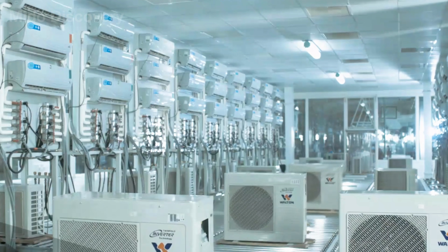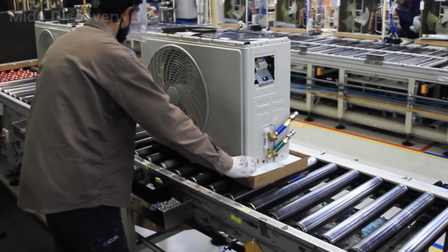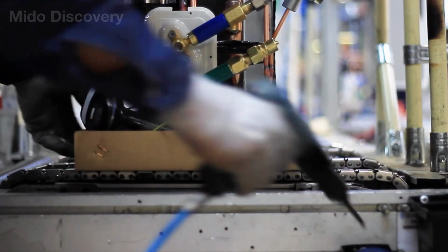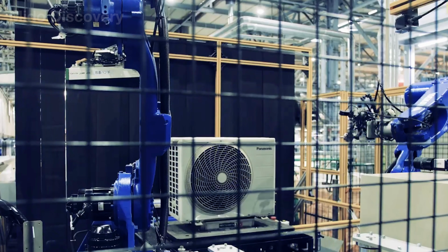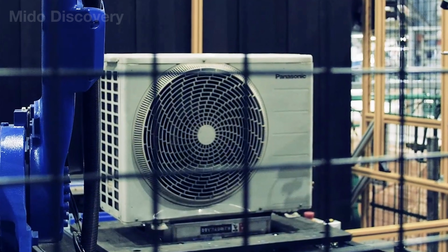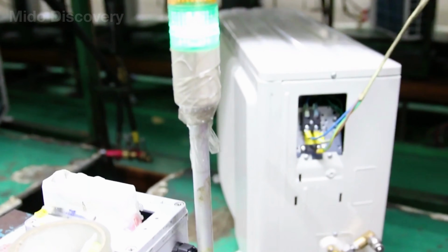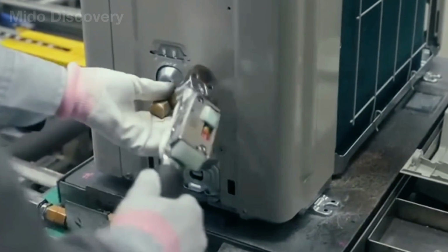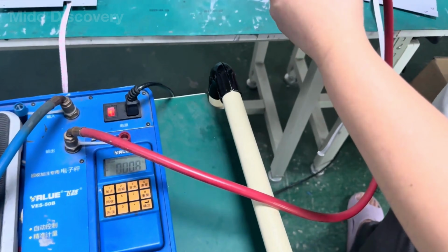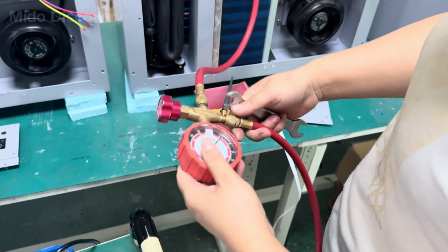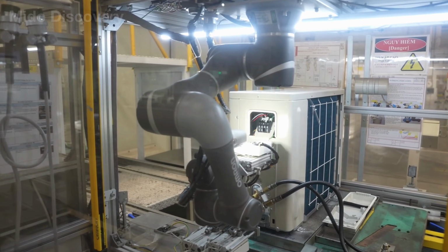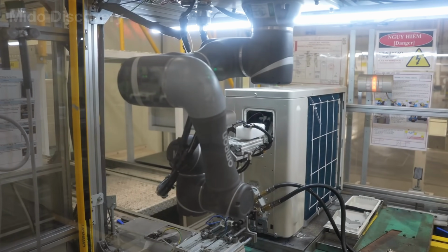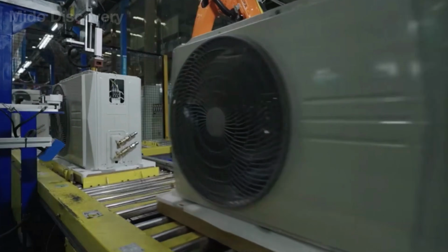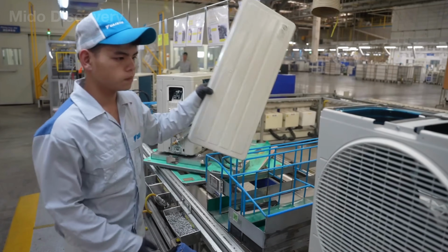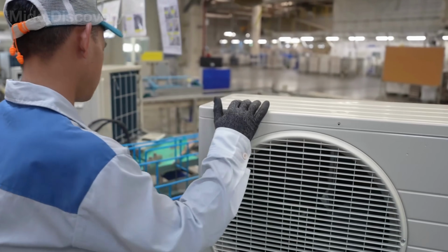At this station, the refrigerant circuit is first pressurized with test gas. An automated detector scans every valve, connection, and brazed joint, searching for leaks that are nearly invisible. Once the system passes inspection, a vacuum pump begins removing the air and moisture trapped inside. The vacuum is held steady for a set period because even a small amount of moisture can react with the oil, cause corrosion, or freeze at the expansion point. Finally, the charging machine reads the model code and dispenses the exact programmed weight of refrigerant. The service tube is then sealed and inspected one last time.